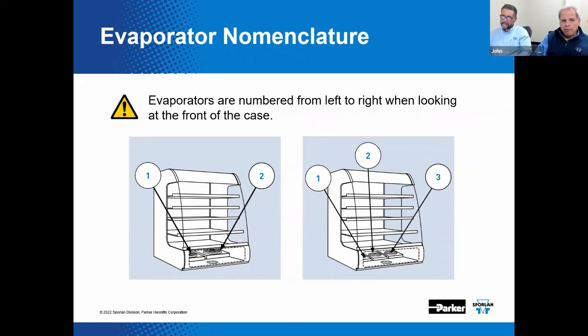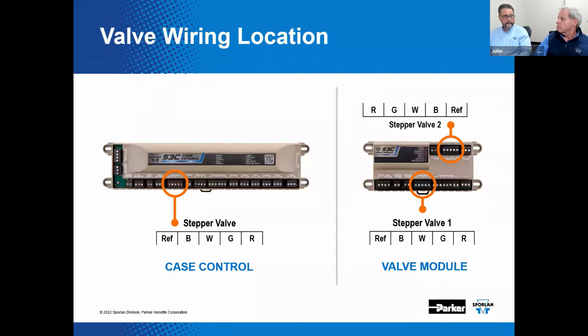Now, here we talk about evaporator nomenclature. I didn't know we needed to have nomenclature for evaporators, but apparently that's important. It is. You see here how we identify evaporator locations and the associated control components in that refrigerated case. While you're looking at the front of the case, we have taken on the technique, if you will, of numbering them, the convention of numbering them from left to right as you're looking at the case from the front. Hence 1, 2, or 1, 2, 3. We can support up to 3 total evaporators in a case with a control and the associated extra components like valve modules. Yep. Kind of makes sense. It makes sense, but we wanted to point that out.